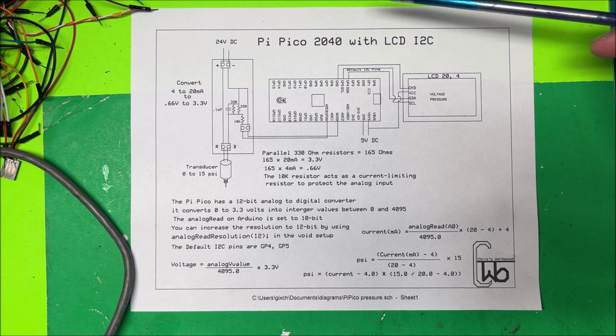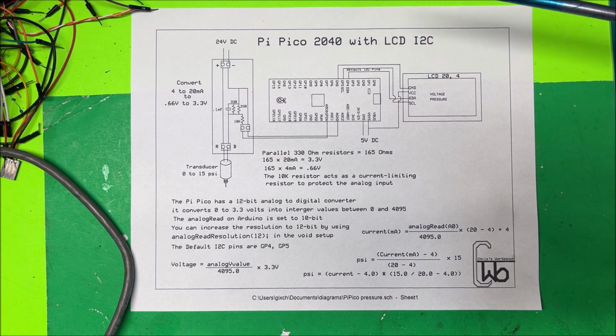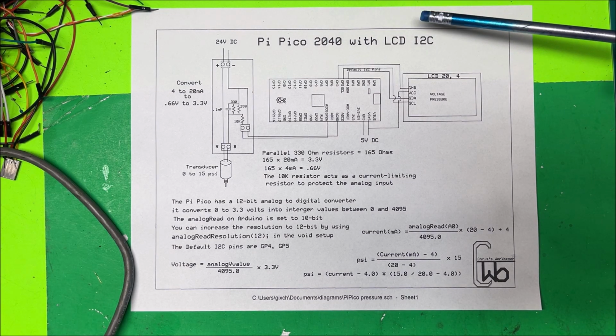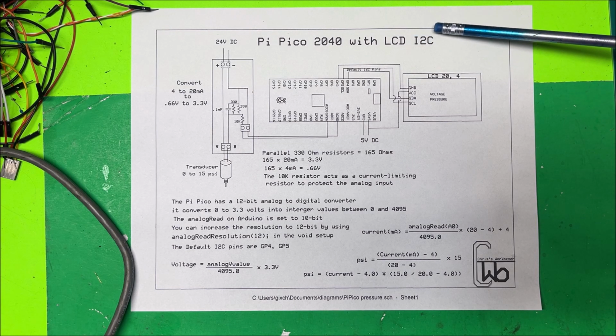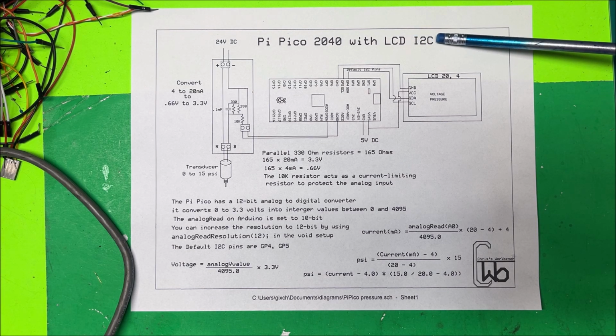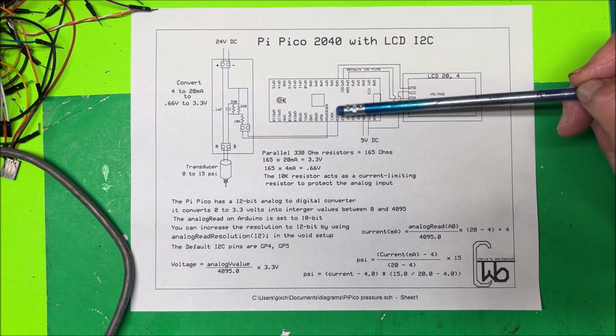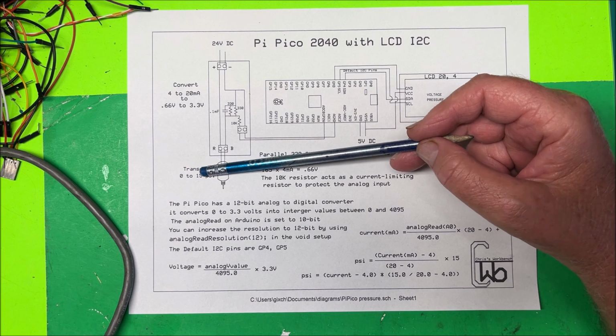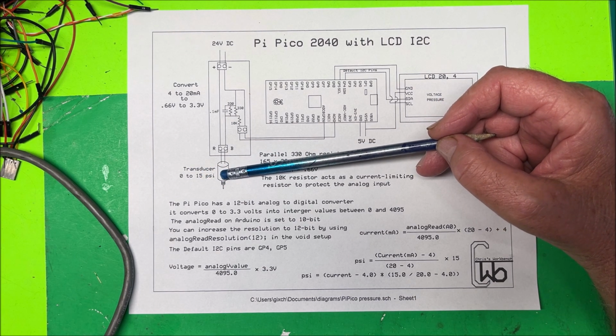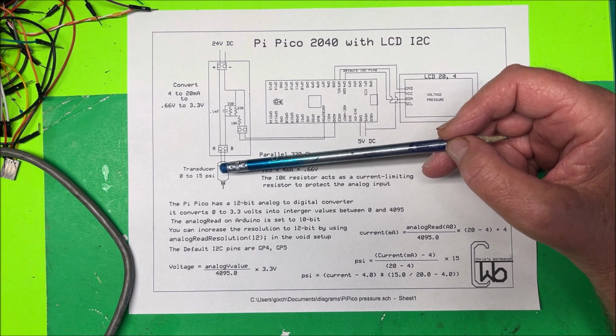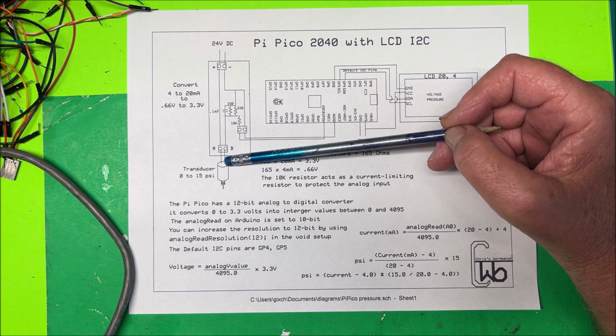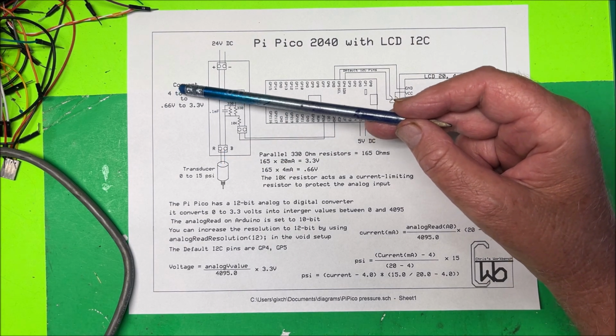Alright, I've got a Pi Pico 2040, and I'm going to use the Arduino IDE, and I'm going to connect a liquid crystal display using I2C. And then I'm going to monitor pressure with it. I have a transducer that's 0 to 15 psi, good for 10 to 30 volts. I'm putting 24 volts through it, and then I have this little converter here. This converts the 4 to 20 milliamps out of the transducer to 0.66 to 3.3 volts.